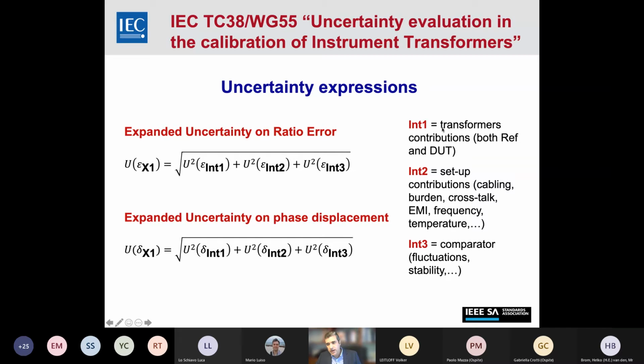The first one is relevant to the contributions provided by the transformers, both reference and device under test. In the intermediate two, we consider all the contributions, many, around 10 contributions coming from cabling, burden, crosstalk, electromagnetic interference, frequency, temperature, and so forth. So all of them have been assumed to be contributions to uncertainty, and for this reason we have propagated them. And then the third one is the comparator, which also provides a contribution to uncertainty.